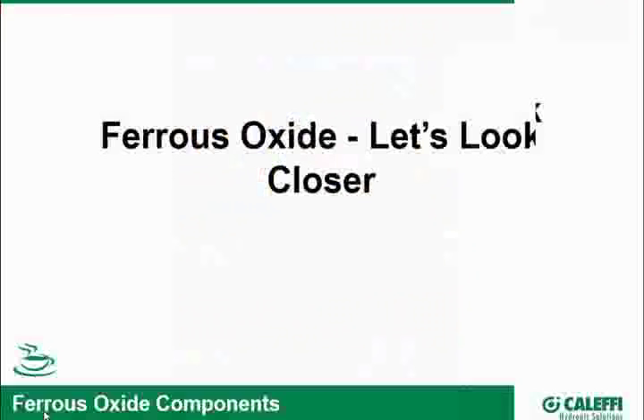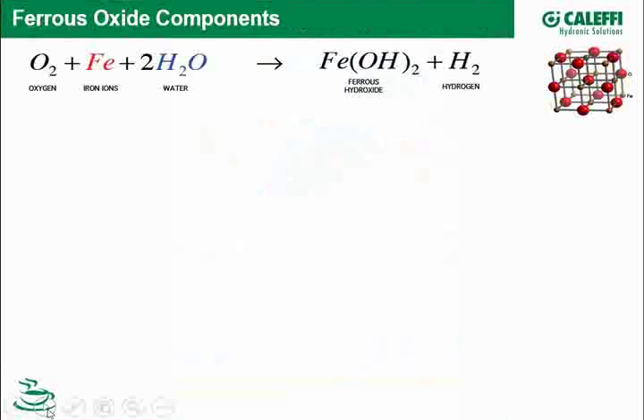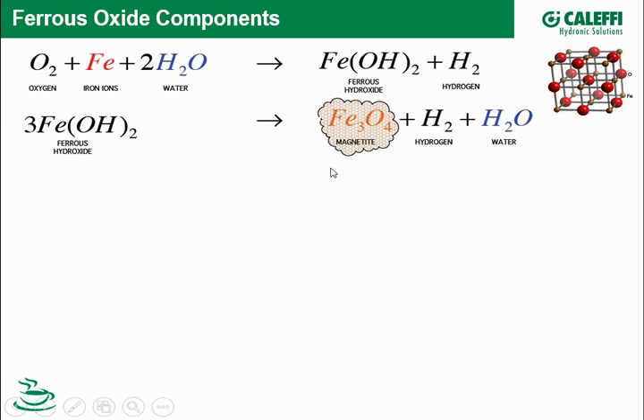From a chemical standpoint, how does ferrous oxide come to exist in our system? Water reacts with iron and oxygen to create ferrous hydroxide and hydrogen. The ferrous hydroxide then continues to react and forms water, hydrogen, and Fe₃O₄ — otherwise known as magnetite.